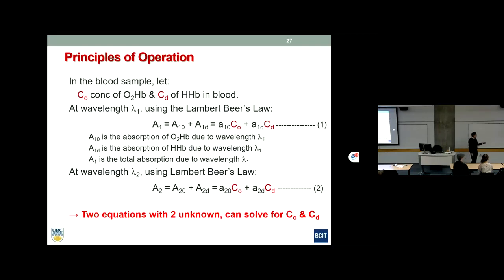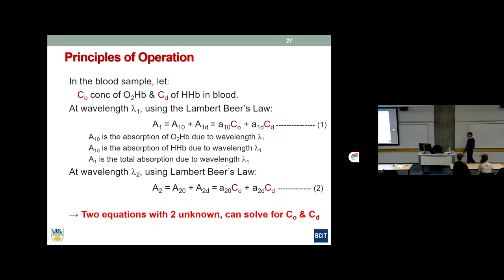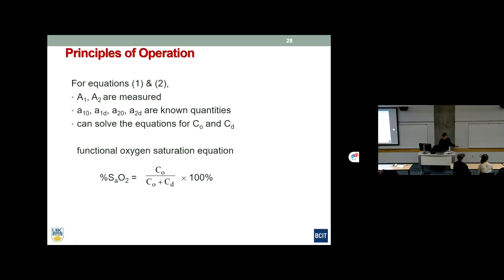Looking at these two equations, there are only two unknowns — the concentrations CO and CD, which are the concentrations of oxyhemoglobin and deoxyhemoglobin; all other values are constants. So with two independent equations and two unknowns, we can solve the system to find CO and CD, and from that calculate SaO2.